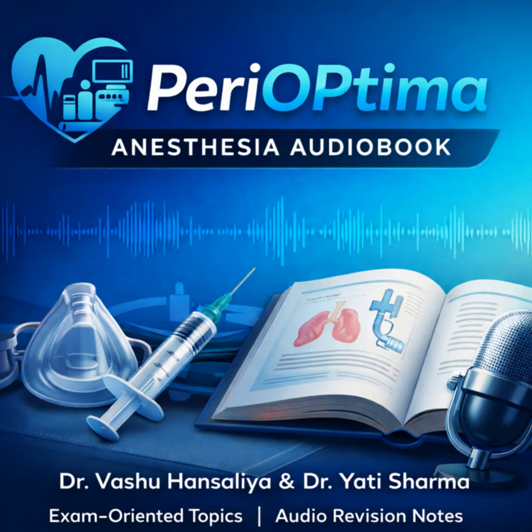What about Mapleson B and C? B and C are often seen as sort of theoretical steps in the evolution towards D, though C does have some historical clinical relevance. For both of them, the FGI and the APL valve are positioned very close to the patient. C is just like B, but with a very short expiratory limb. And efficiency? They're notoriously inefficient in both spontaneous and controlled ventilation.